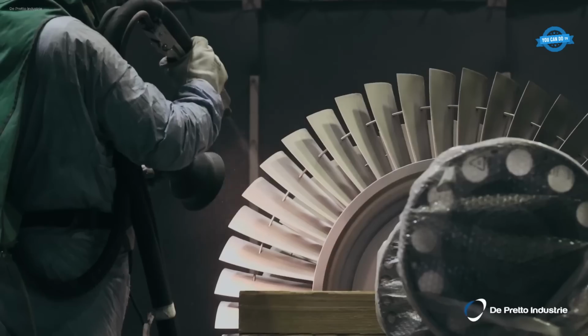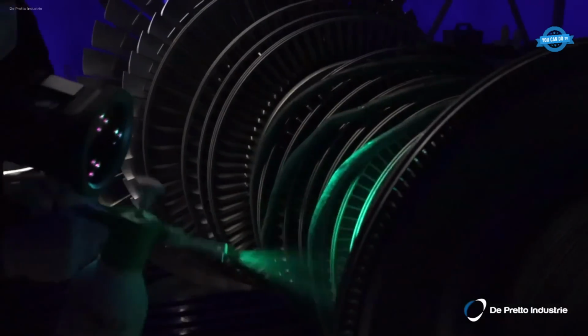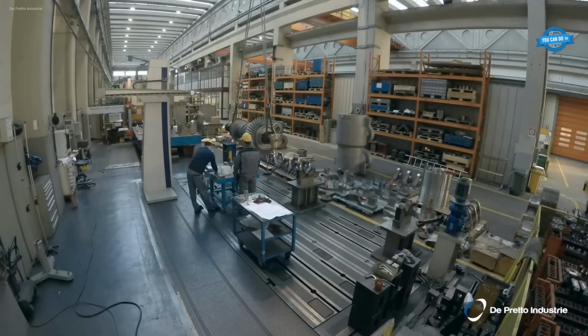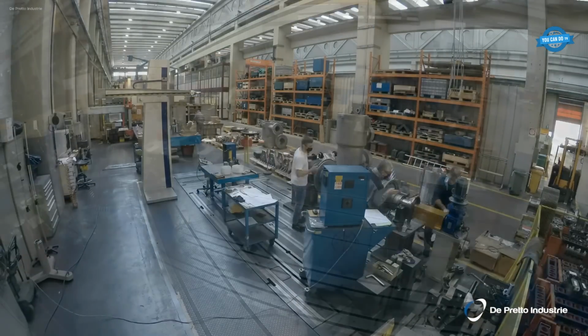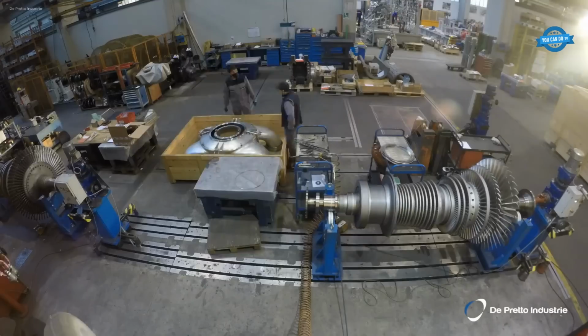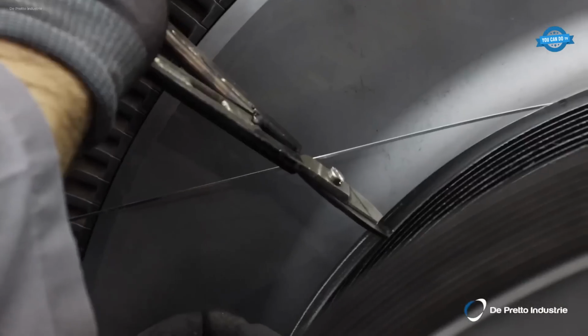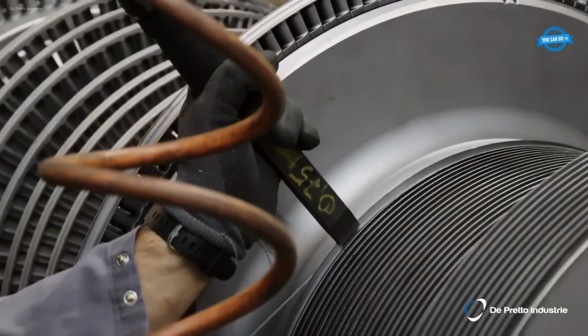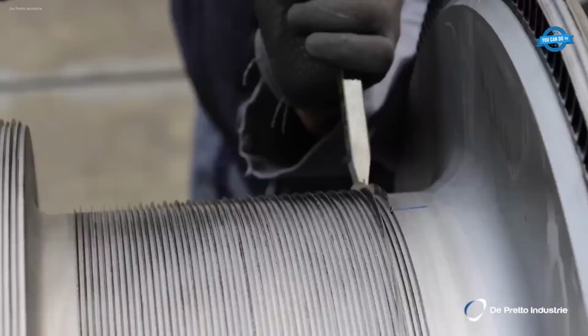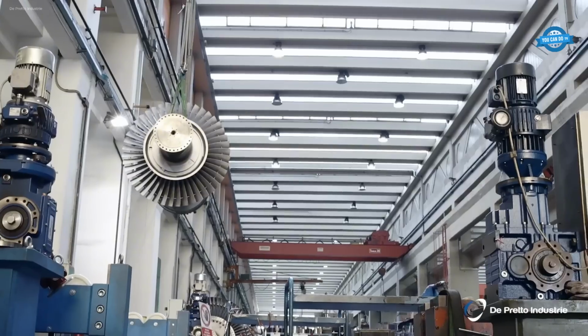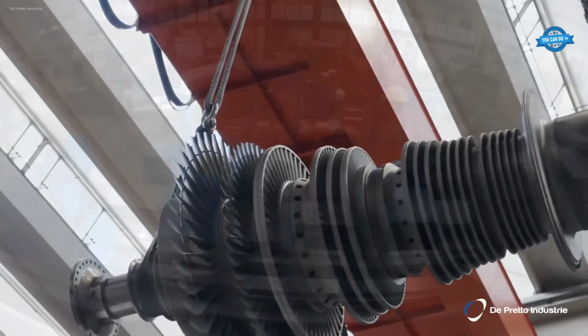Key technical operations included the complete disassembly of the turbine casing and rotor removal. The rotor underwent micro-shot blasting, followed by non-destructive testing, NDT, including magnetic particle and ultrasonic inspection. Dimensional controls were carried out to detect wear, distortion, or imbalance. Any faults were rectified through welding, machining, or component replacement.